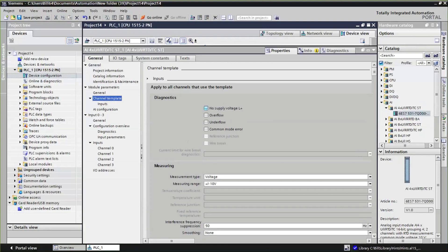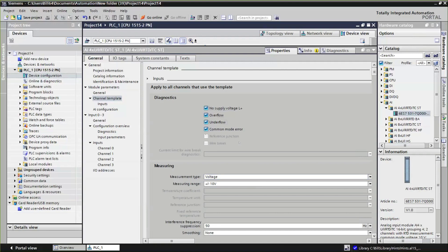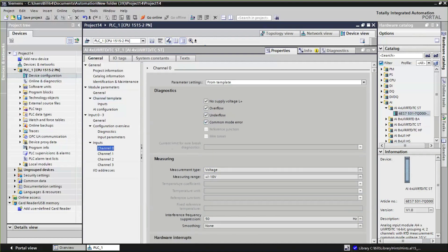If I use this template, that allows me to just one-time set up diagnostic conditions, the voltage levels for the analog input and so forth. And that will propagate throughout all of the four channels on this module because they're coming from that template.